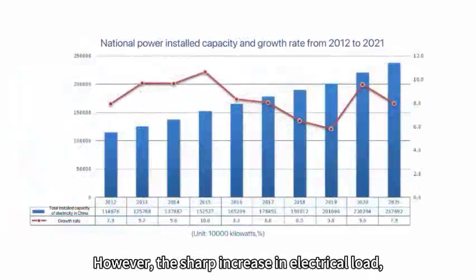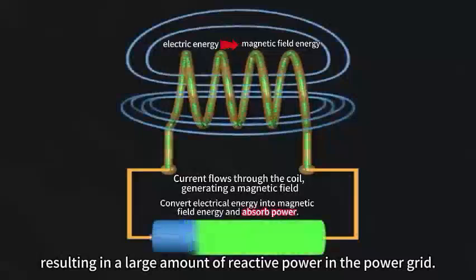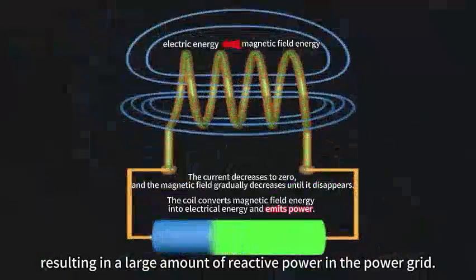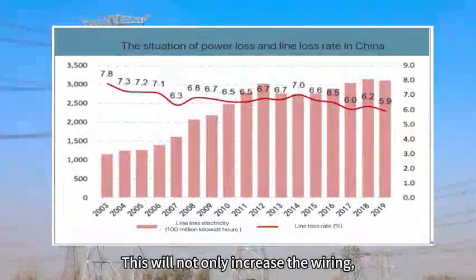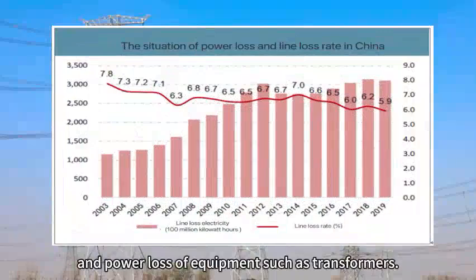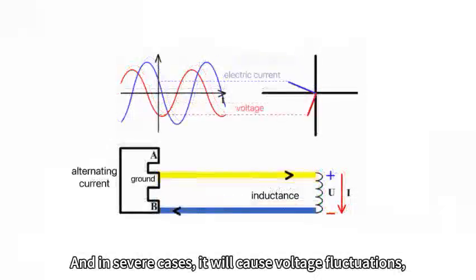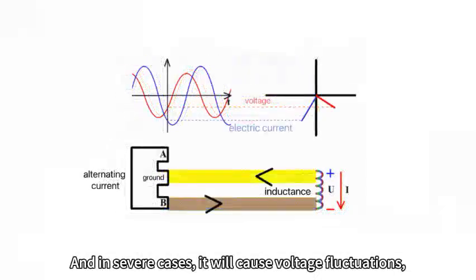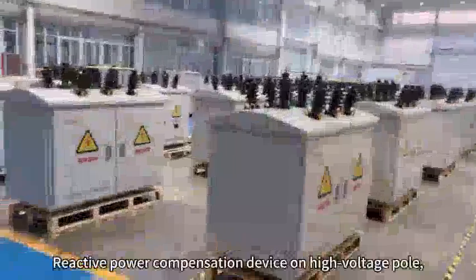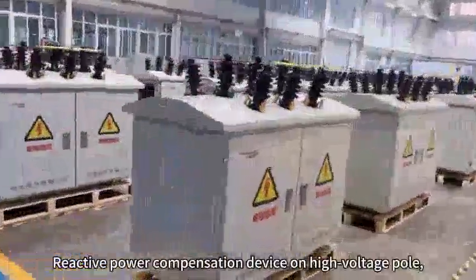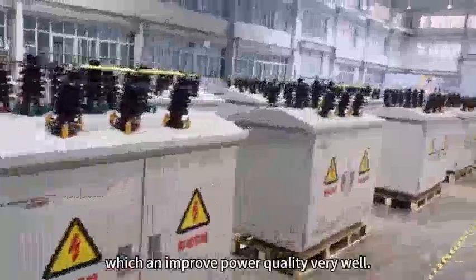However, the sharp increase in electrical load results in a large amount of reactive power in the power grid. This will not only increase the line loss and power loss of equipment such as transformers, but in severe cases will cause voltage fluctuations and affect voltage quality. The reactive power compensation device on a high voltage pole can improve power quality very well.